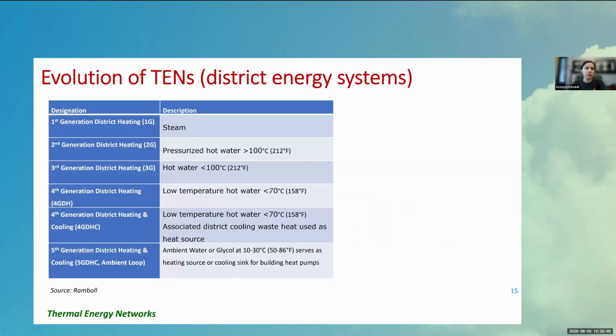So briefly, an overview of thermal energy networks: they're not a new technology at all. We've had district heating, which is what it used to be called, or thermal energy networks of a different kind, for over a century. First generation district heating usually used steam, and in some places these are still being used and functioning. Second generation tended to use pressurized hot water, and these are also still in operation in plenty of places. Third generation used hot water, but not as hot and not pressurized, so below the boiling point. Fourth generation is low temperature hot water — I know this doesn't sound low temperature.